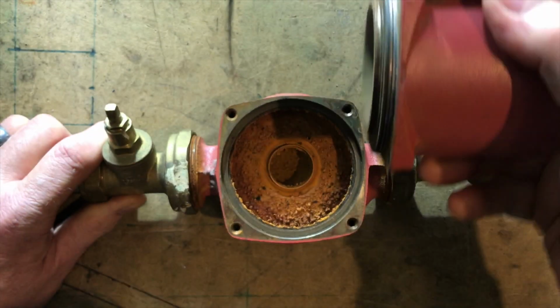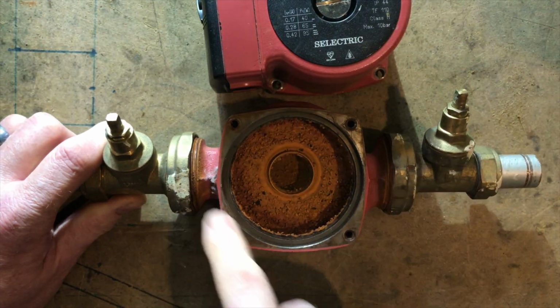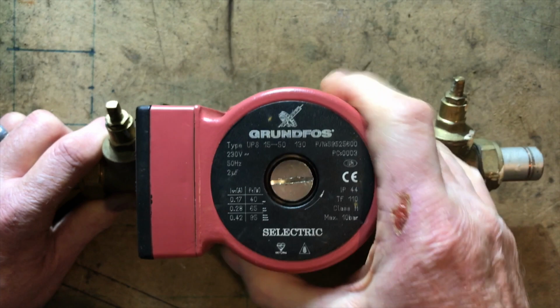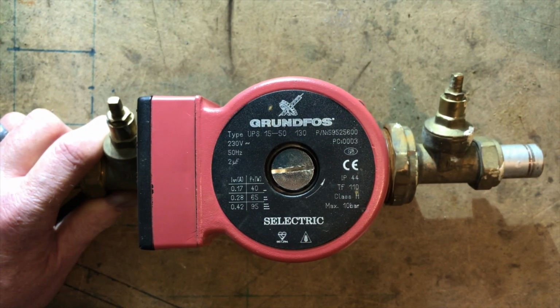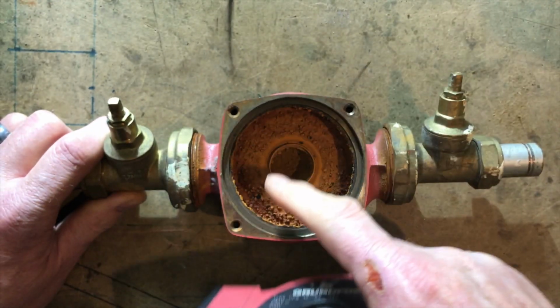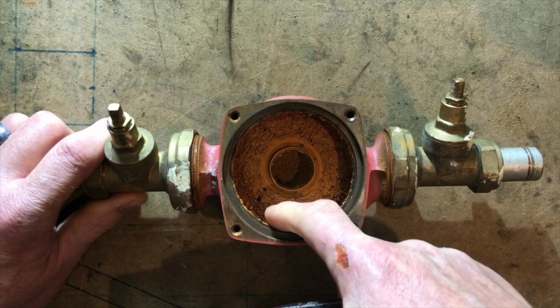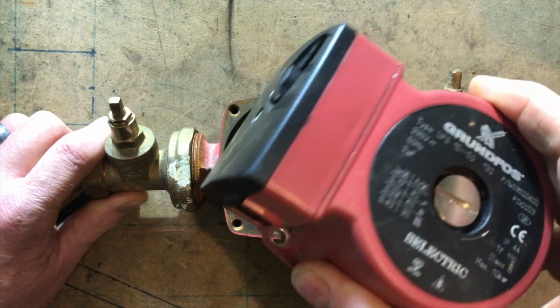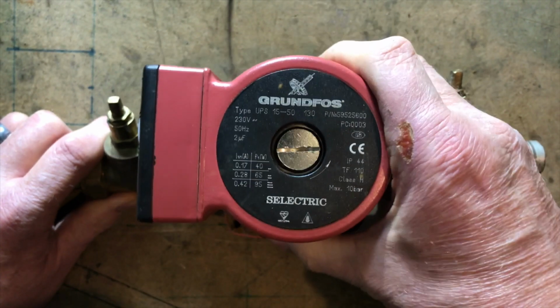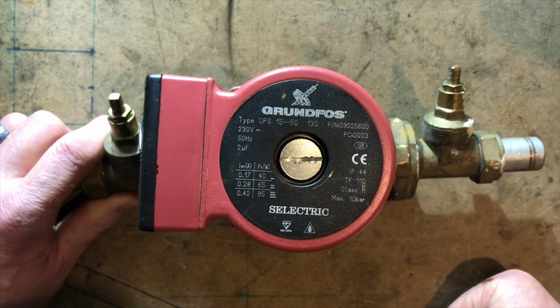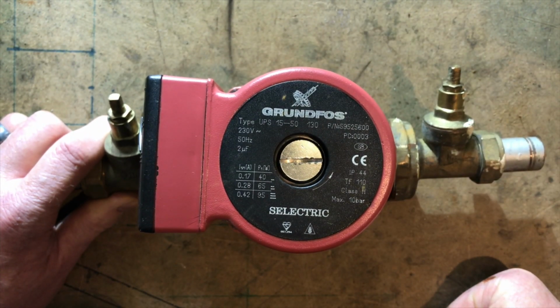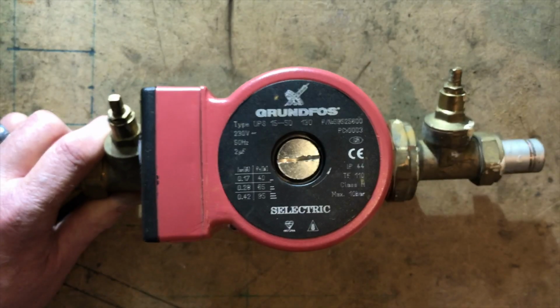Now the other thing as well in the old pumps is the bodies were the same, and you could interchange the heads no matter how old the body was. So if you had a body in position which was in good nick, this definitely isn't, and you just wanted to change the head, then you could just change the head. It was quite handy for when it was inside a combination boiler. So that's a look at the pump head.